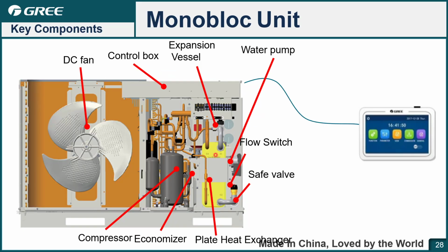Okay. Next one is the monoblock unit. You can see here the DC fan motor, compressor, economizer, plate heat exchanger, safety valve to prevent overly high pressure in the water system, flow switch, water pump for circulating, expansion vessel to keep the water system pressure balanced and store the expansion of the water, control box, and also the e-heater at the bottom of the chassis.